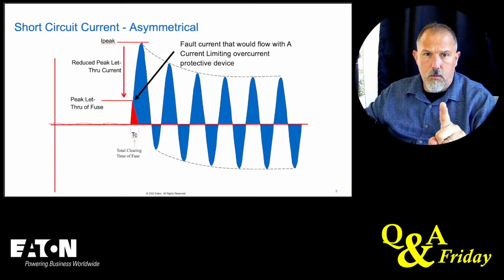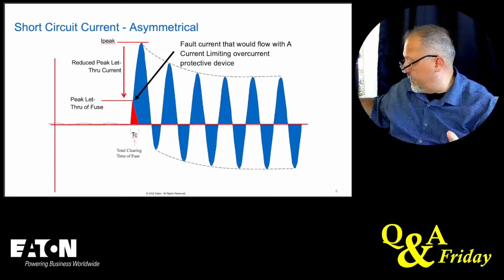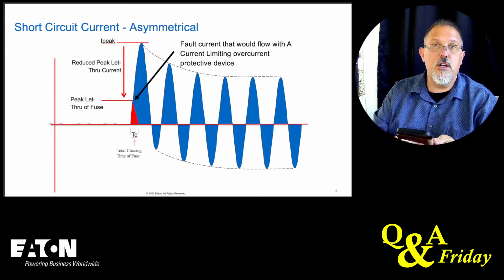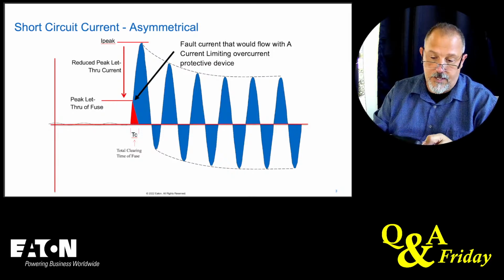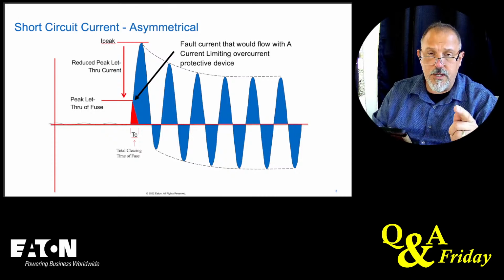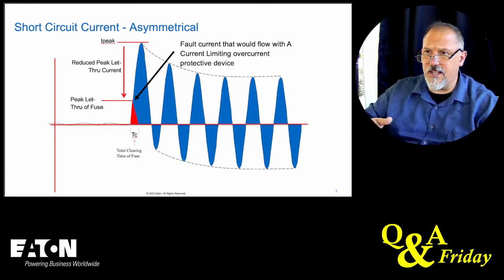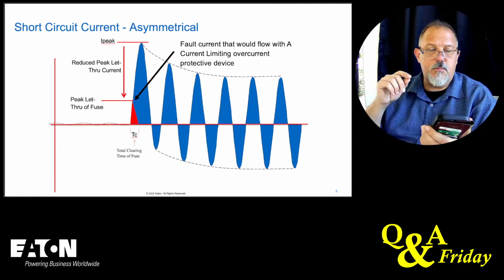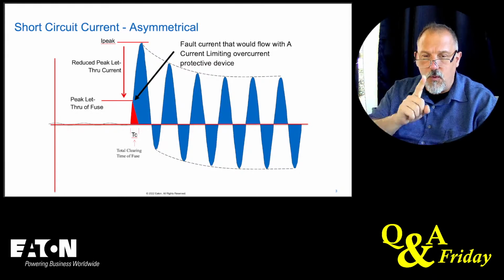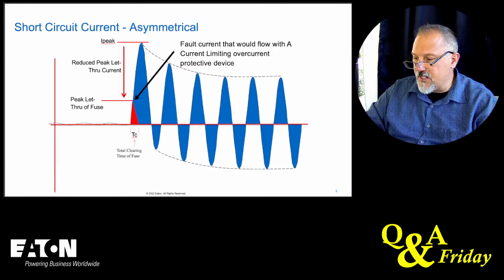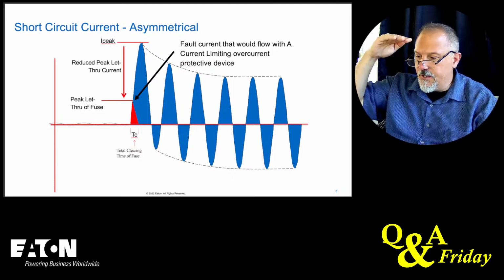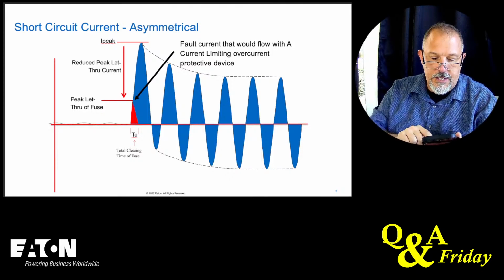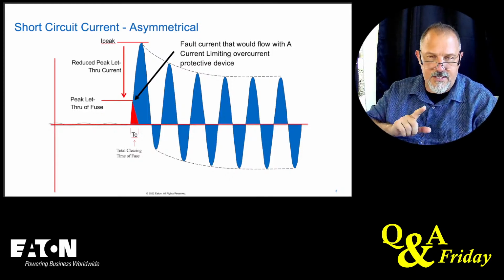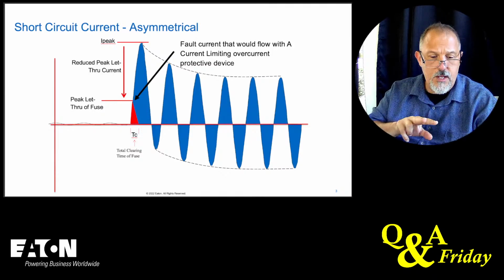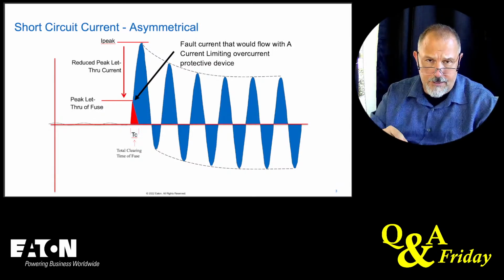One cycle, this is a 60 hertz system. So 60 hertz, one cycle is 1 divided by 60, right? And if you take 1 over 60, it's 0.016 seconds. We always say 0.016 seconds, but it's 0.0167. So one cycle, meaning a half a cycle, just that hump on the very top portion of that trip curve, is 0.0167 divided by 2, it's 0.0083.